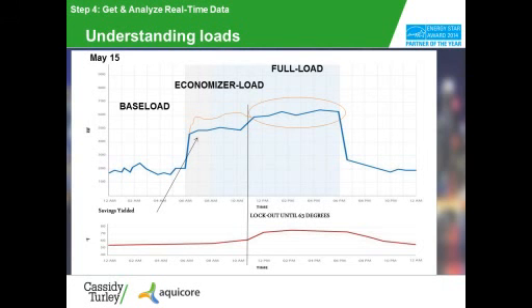And then we see 6 p.m., the mechanical system goes off and the load drops down. And it has that very traditional look, that gradual slide into 10 p.m., which is a pretty normal thing to see. That's when housekeeping's coming in, late workers are trickling out, lights in the building are still on. Eventually, as cleaning gets the floors clean, lights are turned off. Security's becoming more stable, and now we're at 10 p.m. and the base load really starts right around 10, 10:30, 11, 12, depending on the building.